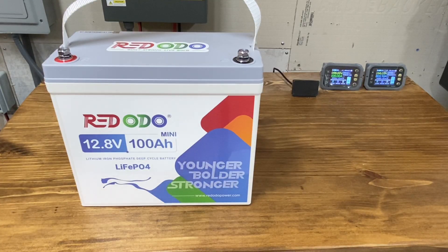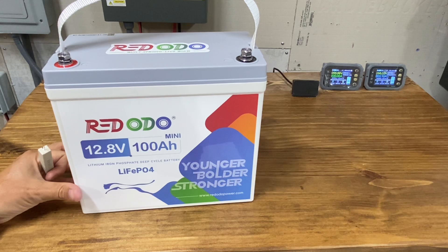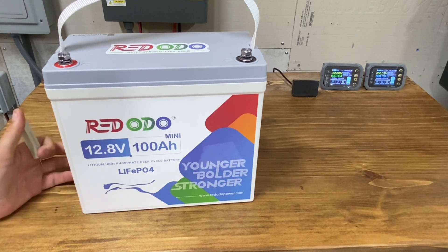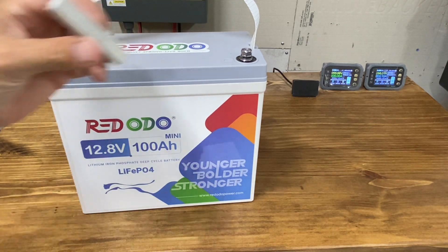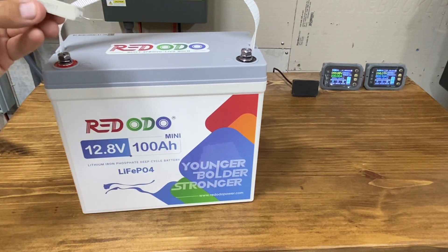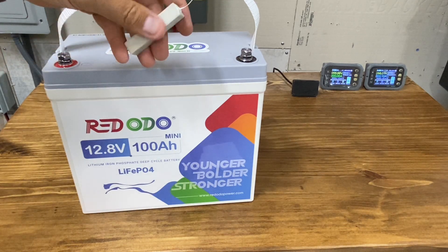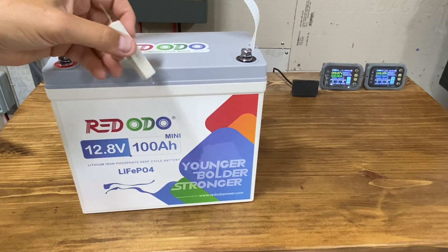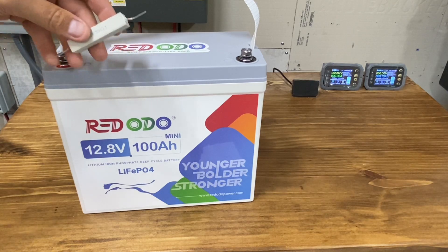Maybe you don't have a rack battery, or maybe you have a small 12-volt system with lithium iron phosphate like this little Redodo Mini, and you need to pre-charge your capacitors in whatever inverter you have. You might have a 24-volt system with two of these. That's where these resistors come in. You can buy really cheap ones on Amazon — I think this is a 30-ohm. You can get ones with aluminum covers, fancier ones, or you can build your own.